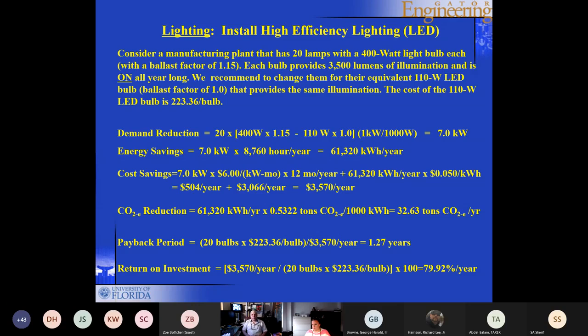So one of the recommendations that we do is lighting, install high efficiency lighting. So let us take an example of a facility, manufacturing plant that has 20 lamps. Each lamp is a one bulb lamp, meaning that it has one bulb, and that bulb is a 400 watt light bulb. The ballast factor is 1.15. Again, I'm giving examples here from, these are actually numbers from a real facility. Each bulb is going to provide 3,500 lumens of illumination, and it's on all year long. So the assumption is that we're going to leave it on all year. That's 365 days, 24 hours a day.